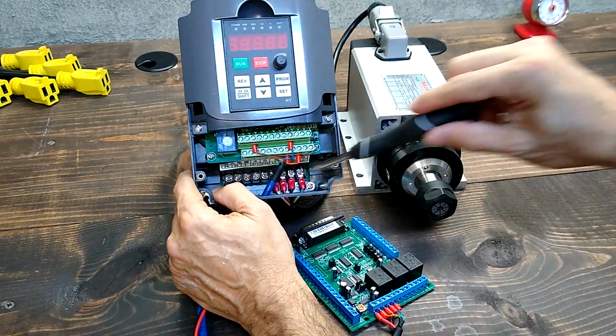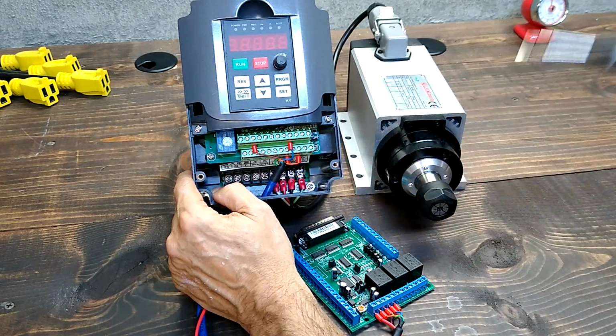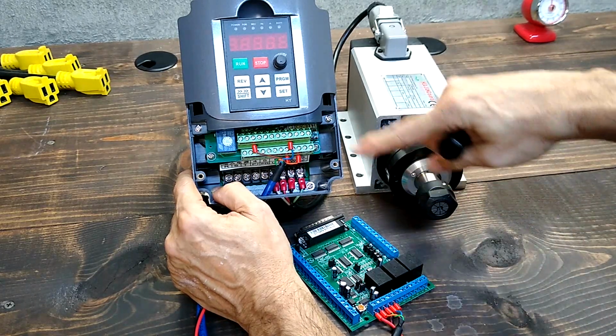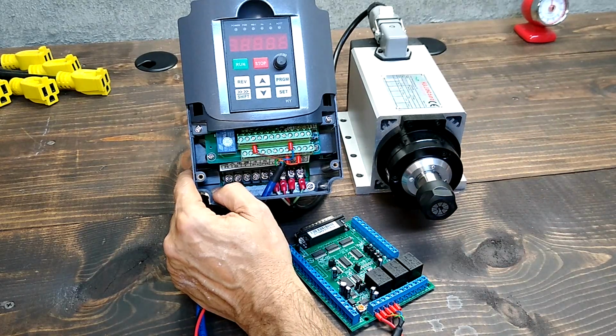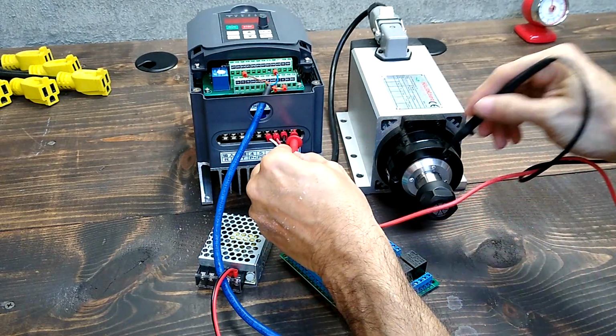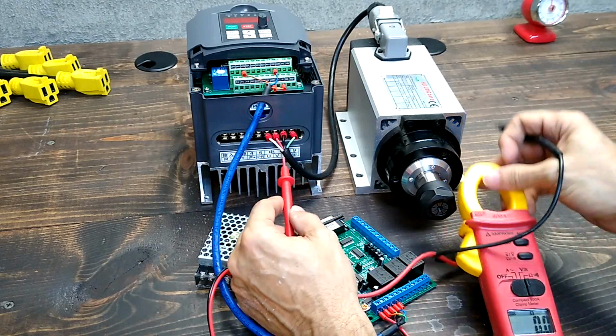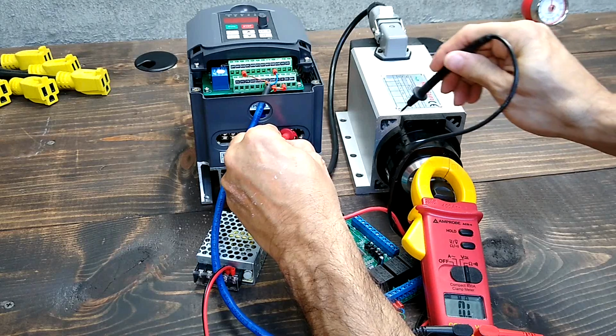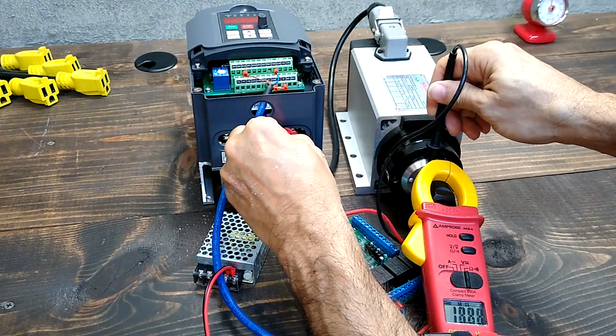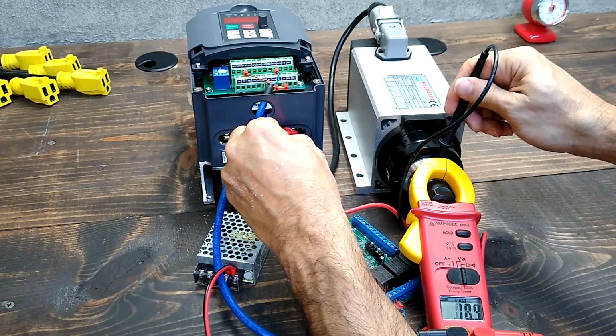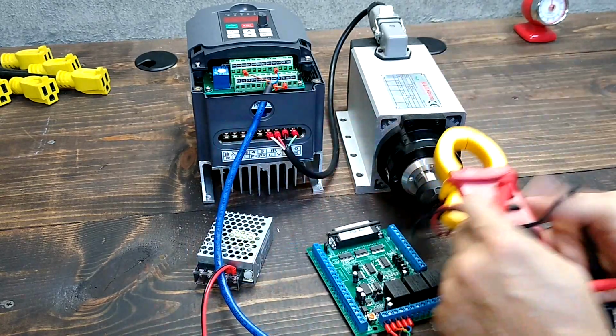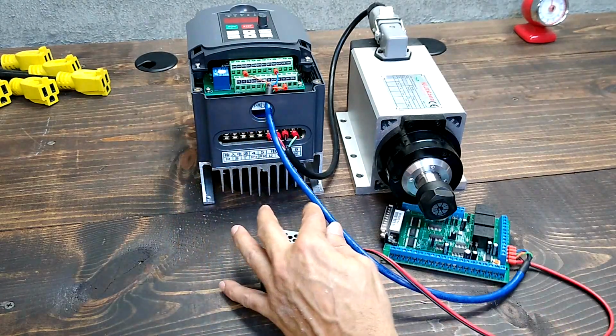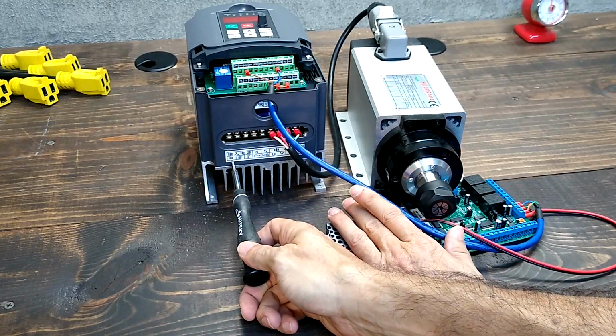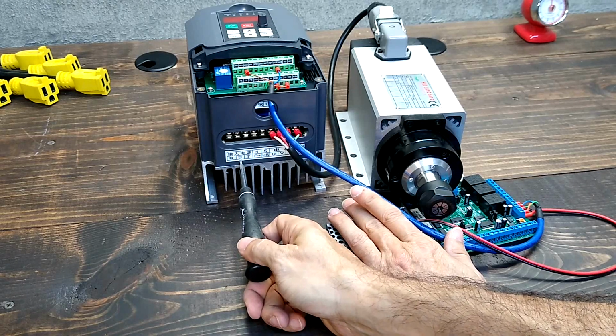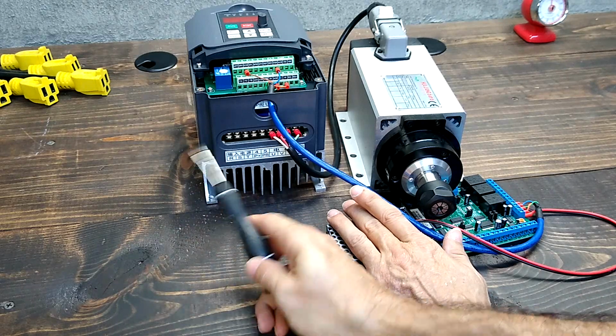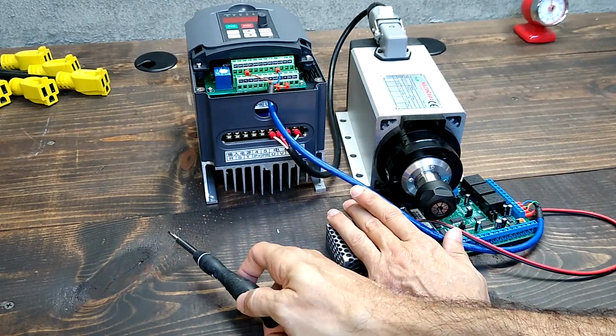We have 4 wires to connect the spindle. The first 3 could be in any order. If the spindle is running counterclockwise, we will change the order of the connection until spindle runs clockwise. The 4th wire is ground, and we can determine this by checking continuity between the spindle and one of the 4 wires. To power the VFD, we will connect live, neutral, for 220 AC 2-phase, and live, neutral, for 110 AC single phase.